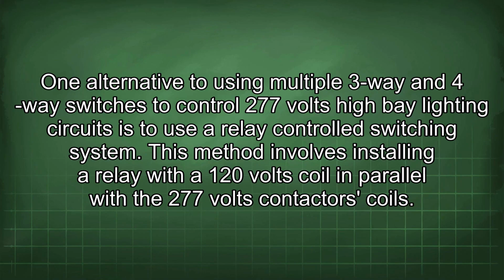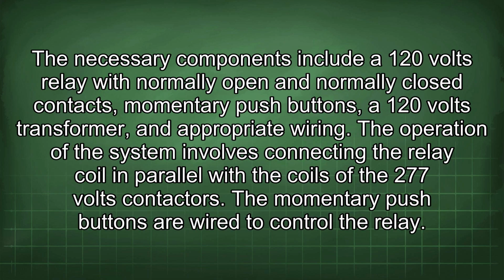One alternative to using multiple 3-way and 4-way switches to control 277 volts high bay lighting circuits is to use a relay-controlled switching system. This method involves installing a relay with a 120 volts coil in parallel with the 277 volts contactors coils. The necessary components include a 120 volts relay with normally open and normally closed contacts, momentary push buttons, a 120 volts transformer, and appropriate wiring.